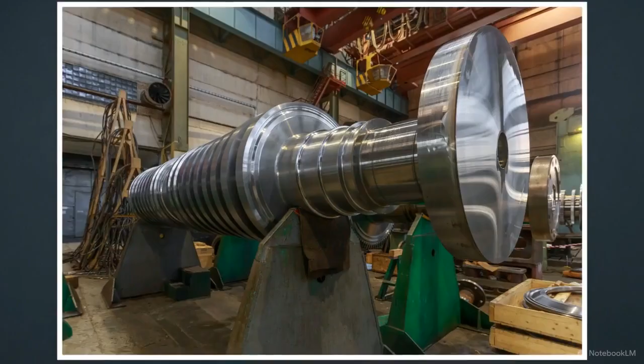When those invisible electrical waves reached a traditional thermal power plant, they perfectly matched the mechanical resonance of the plant's hardware. The electrical flutter excited violent torsional vibrations in the equipment, twisting the solid steel turbine shafts until they physically cracked. To prevent further destruction, protective relays slammed shut, instantly ripping 3 large generation units offline and plunging the region into a sudden 1,280 megawatt blackout. Similar mechanical fractures have since been recorded in Vietnam and Russia.